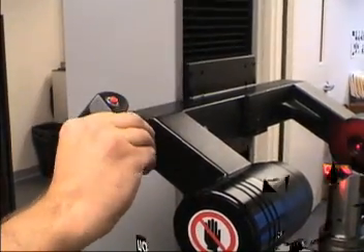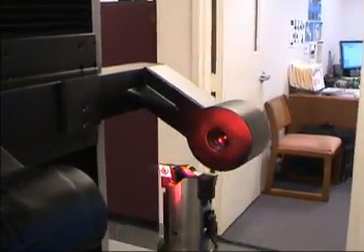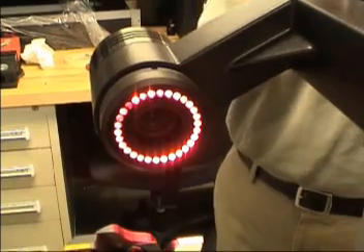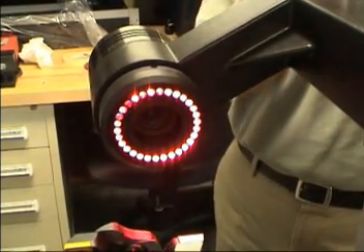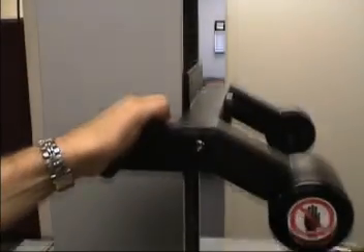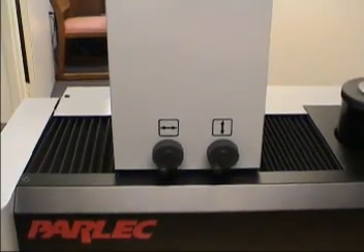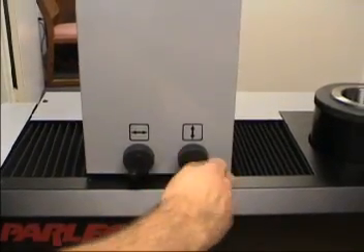Inspection light option. The inspection light control, located on the camera arm, turns on the inspect light and controls the light intensity to ensure the optimal picture quality. Fine adjustment brake option. The button located on the hand grip releases the brake and allows the axis to move freely. Turning the fine adjustment knobs will move the axis in very small increments.